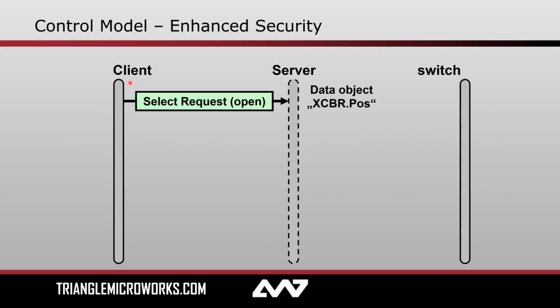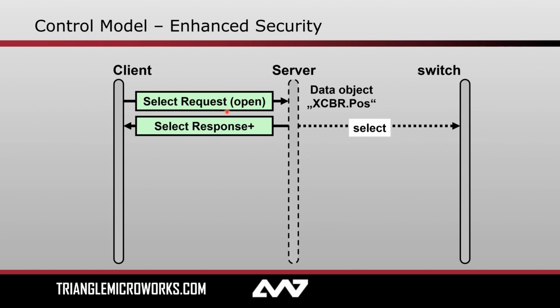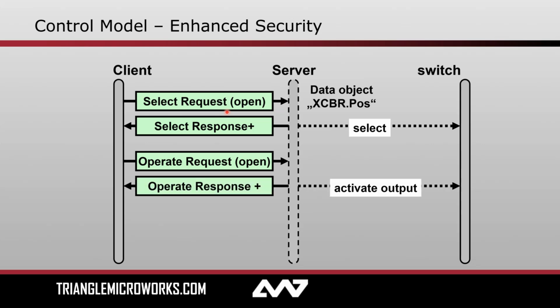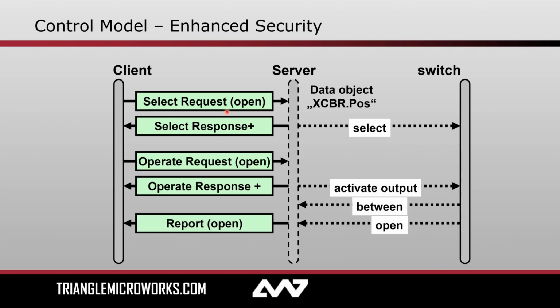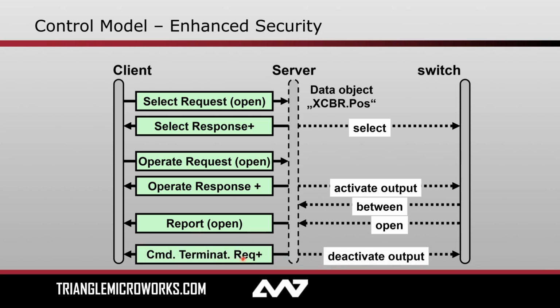So in this example, my client issues the request to open, just like we saw. Oh, I'm sorry, this is not like we saw before. Before we went directly to operate. Here we're requesting permission to operate it, reserving the right to operate this control, if you will. Once we get the select response in the affirmative from the server, we can now operate our breaker, requesting the output to be open. This part is shared between all variants. And then finally, again shared between all variants, we see a successful answer coming back from the server to the client, letting us know that, yes, I actually tried. But it's actually this command termination request down there at the bottom, that last service that I spoke about on the last screen, that tells us whether or not my control was a success.